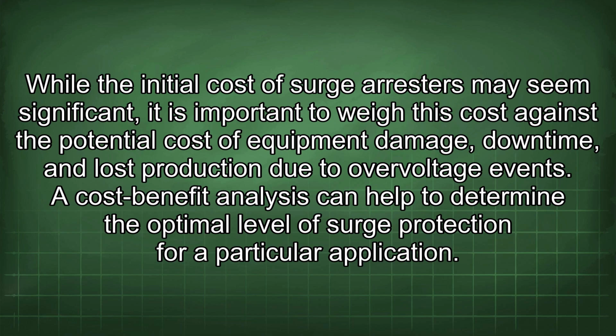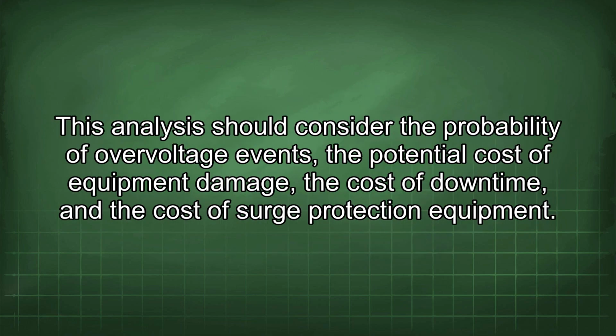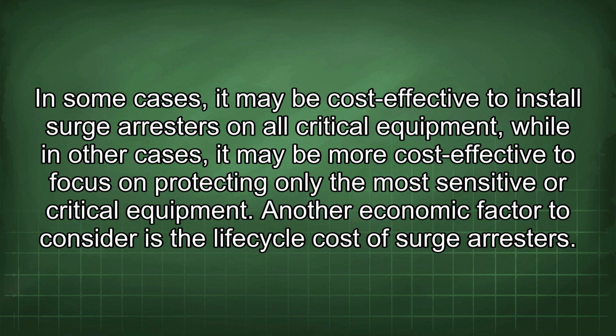A cost-benefit analysis can help to determine the optimal level of surge protection for a particular application. This analysis should consider the probability of overvoltage events, the potential cost of equipment damage, the cost of downtime, and the cost of surge protection equipment. In some cases, it may be cost-effective to install surge arresters on all critical equipment, while in other cases, it may be more cost-effective to focus on protecting only the most sensitive or critical equipment.